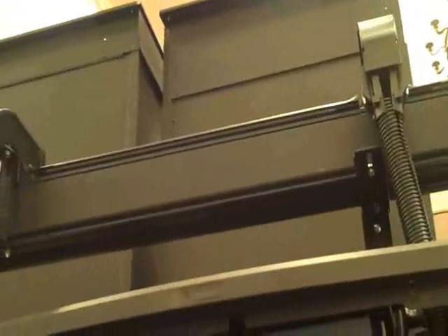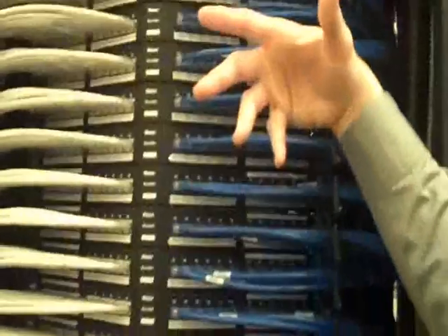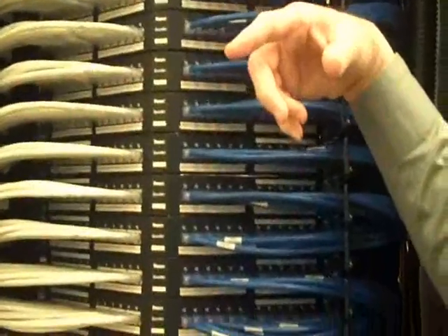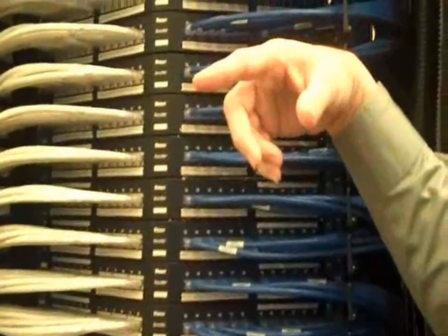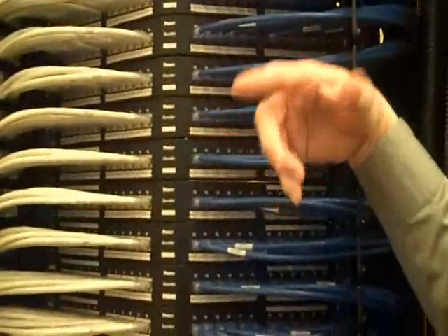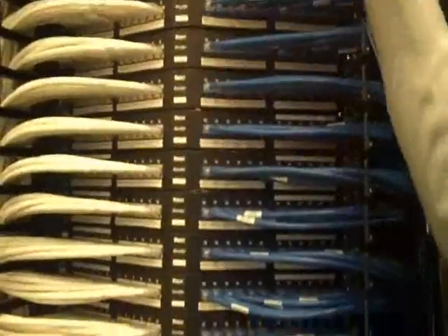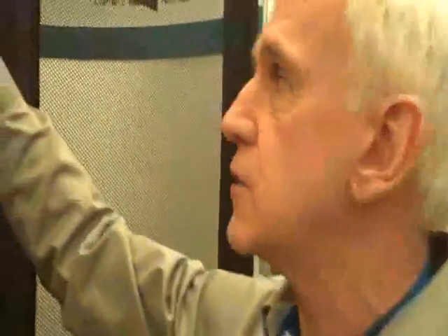It increases the efficiency of the CRAH, the computer room air handler, by increasing the temperature delta T across it. So an Emerson Liebert computer room air handler will benefit from increasing that delta T across the heat exchanger, as well as it prevents things like wraparound of the exhaust air into the inlet of the device.